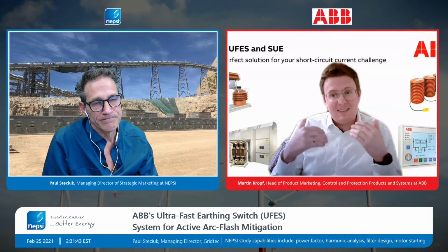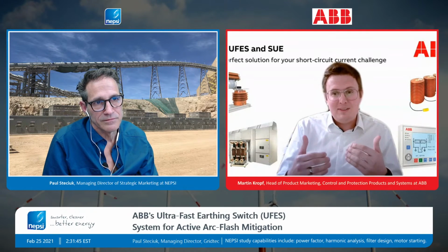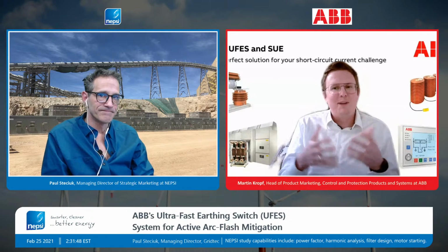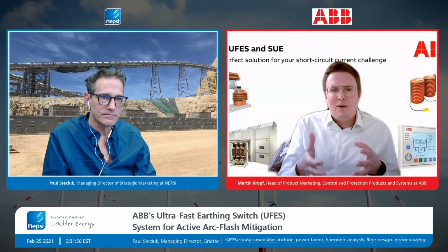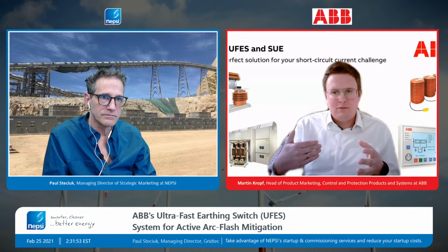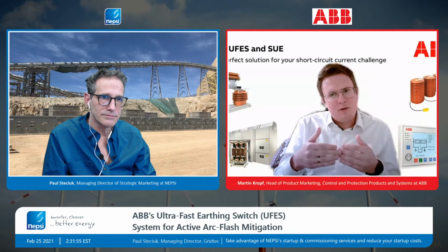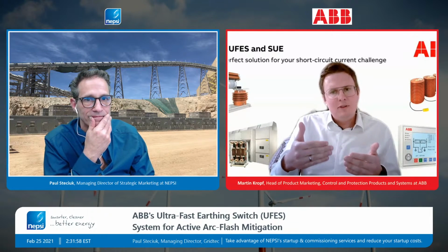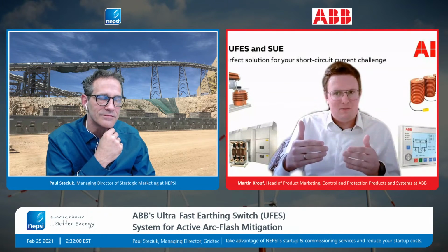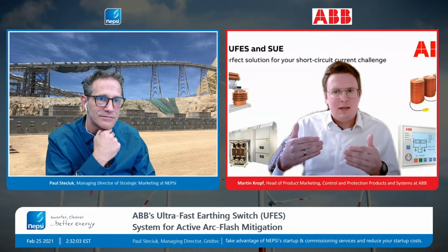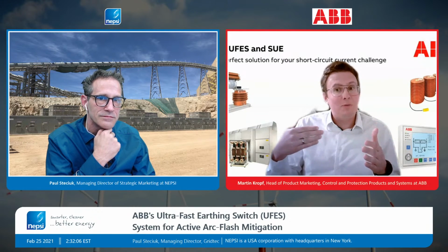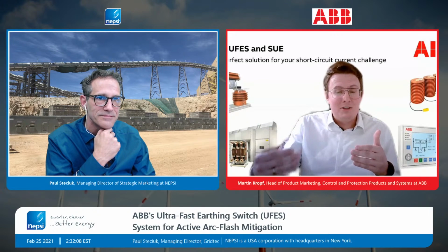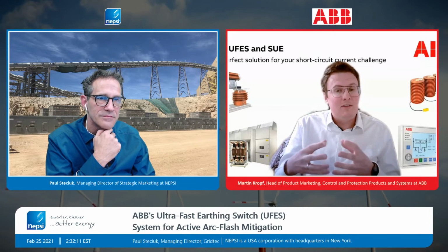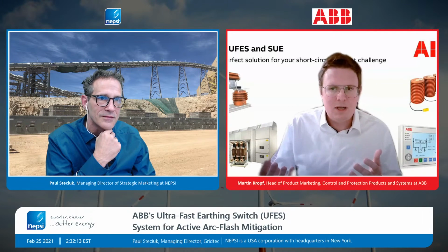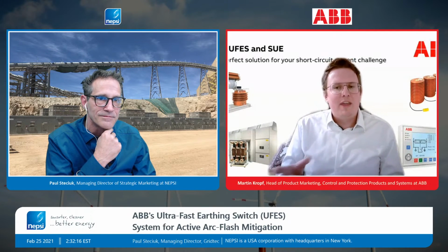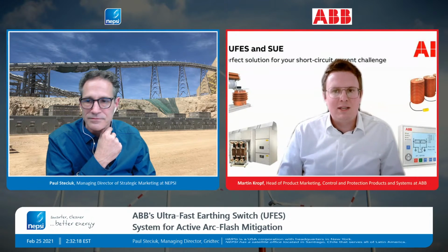If you are at site, there is the risk of human errors, and you open the door. If you're talking arc-proof design, the passive arc-proof design is not helping you anymore once the door is open, because when you enter it's not really helping you. So UFES is also on then, and it's also protecting you in case you are at site with open doors.